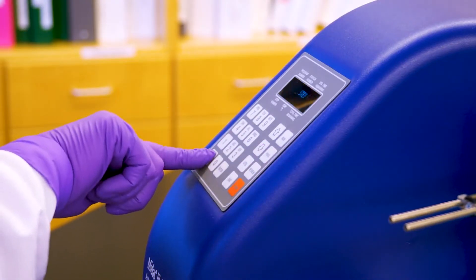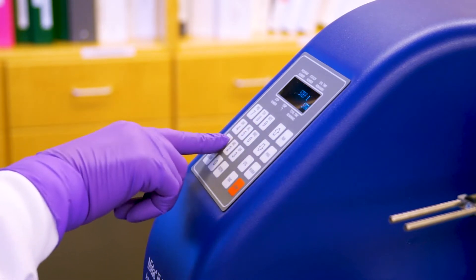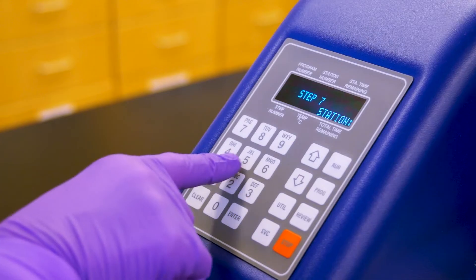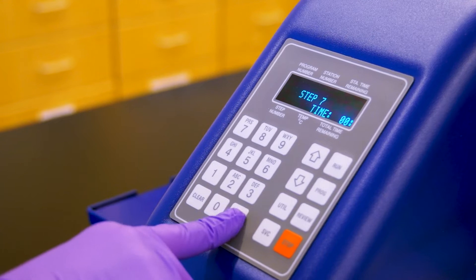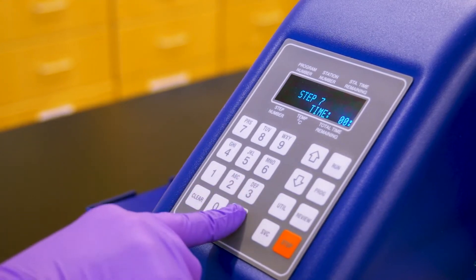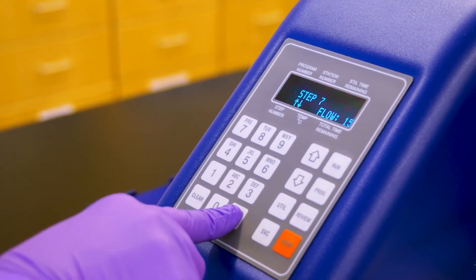The instrument is run by a microprocessor which allows you to enter your staining protocols quickly and easily using the keypad. You can program and store up to nine procedures that can then be selected with a single keystroke.